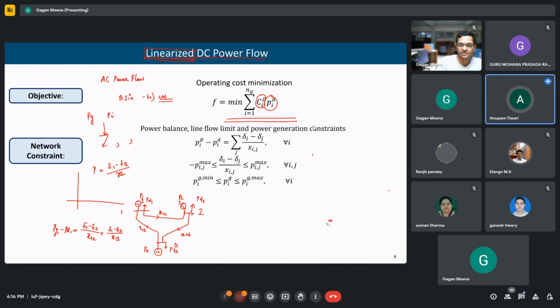No, line capacity. We have defined delta, where power equals the angle difference divided by reactance. This equals the line flow. We want the line flow to be within its maximum limit, so it should always be less than or equal to P max, in both directions. If we consider the direction from 1 to 2 as positive for line flow, then flow in the reverse direction will be negative. So in the reverse direction also it should not exceed its limit, that is why we have a negative here.